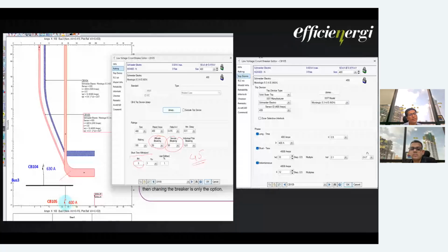This is given by the manufacturer. This is particularly the NSX breaker. And why I'm saying the coordination was wrong is, as I said earlier also, the breaker itself is not allowing you to enable or disable the instantaneous value. So this instantaneous was not able to be disabled from the breakers.